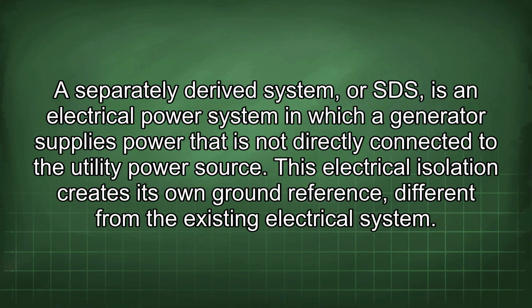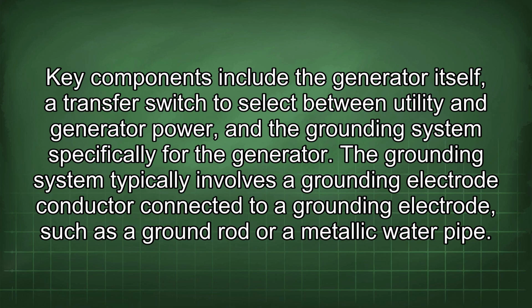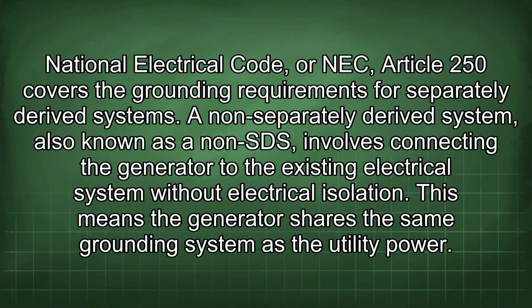A separately derived system, or SDS, is an electrical power system in which a generator supplies power that is not directly connected to the utility power source. This electrical isolation creates its own ground reference, different from the existing electrical system. Key components include the generator itself, a transfer switch to select between utility and generator power, and the grounding system specifically for the generator. The grounding system typically involves a grounding electrode conductor connected to a grounding electrode, such as a ground rod or a metallic water pipe. National Electrical Code, or NEC, Article 250 covers the grounding requirements for separately derived systems.